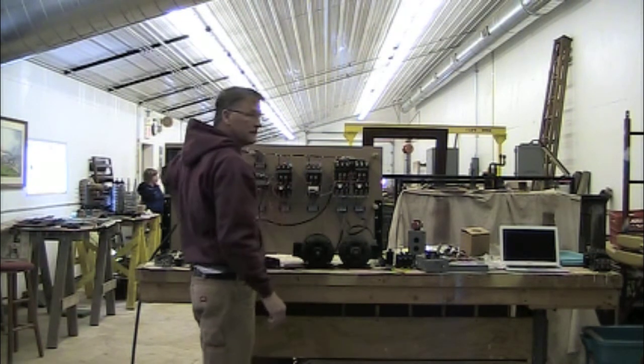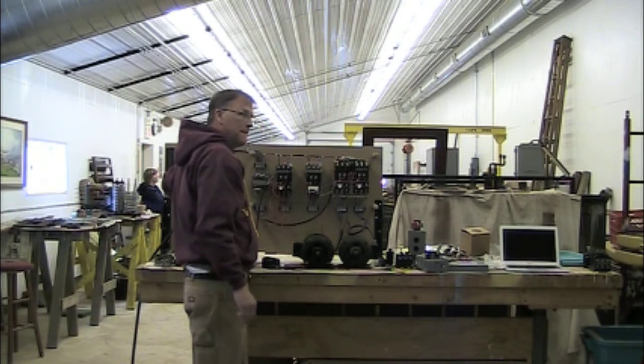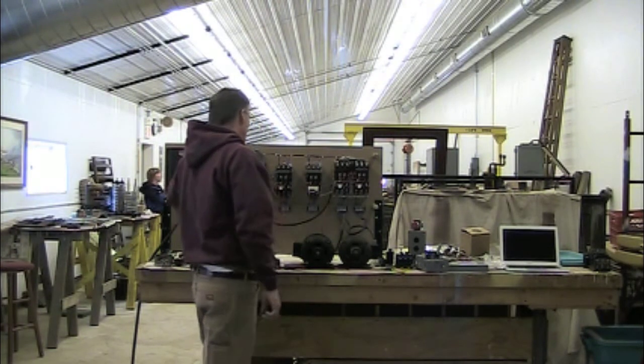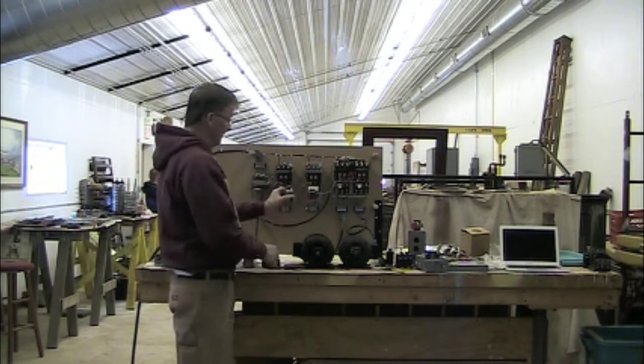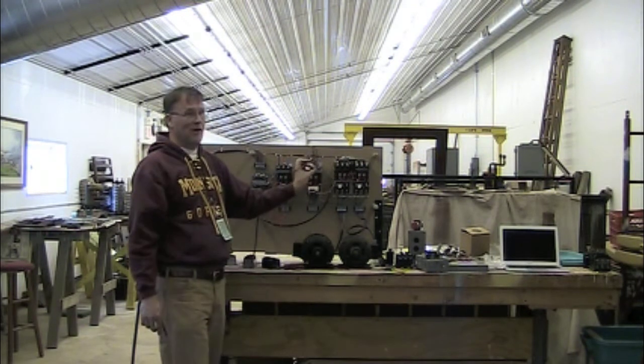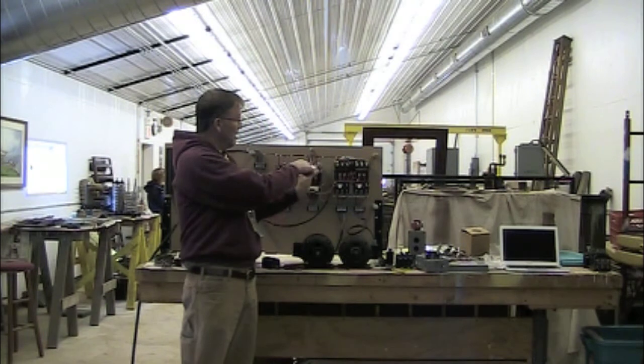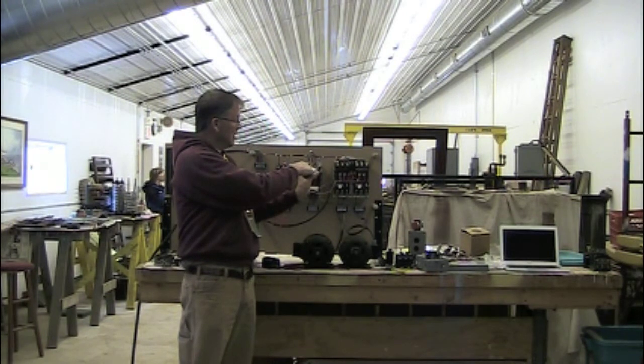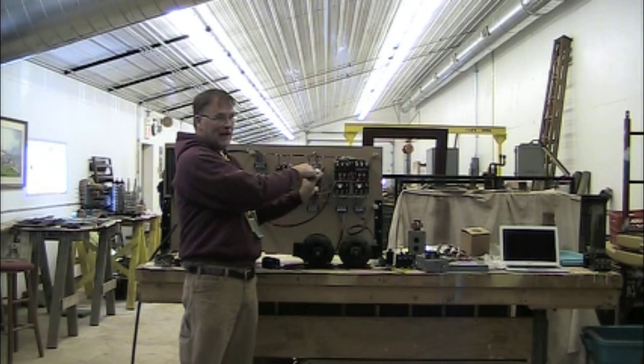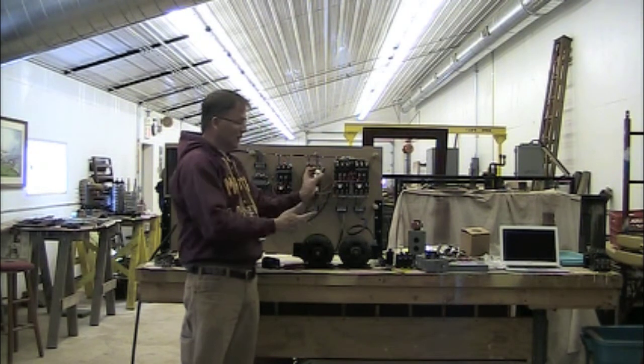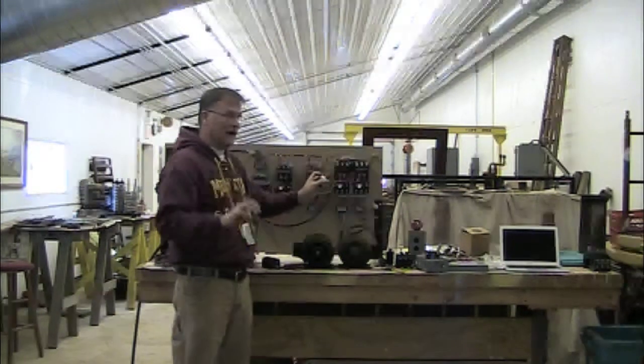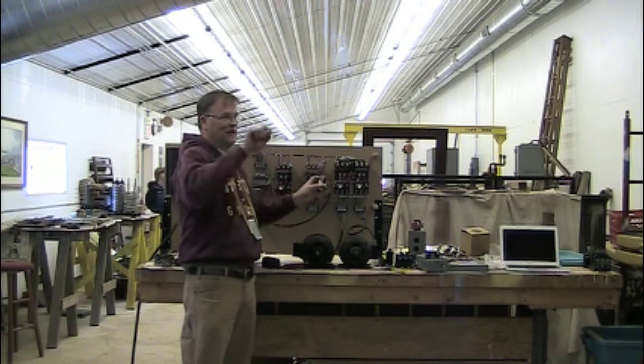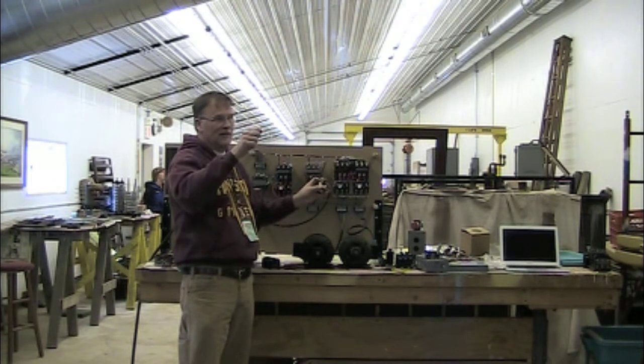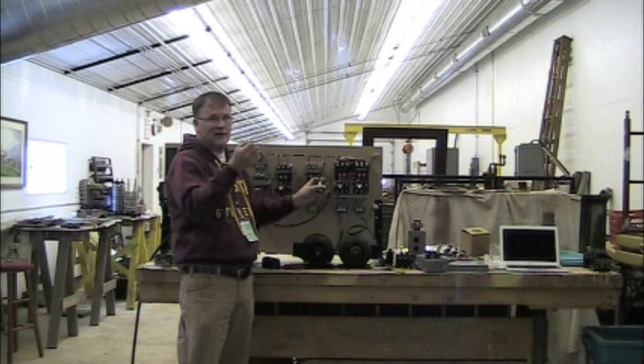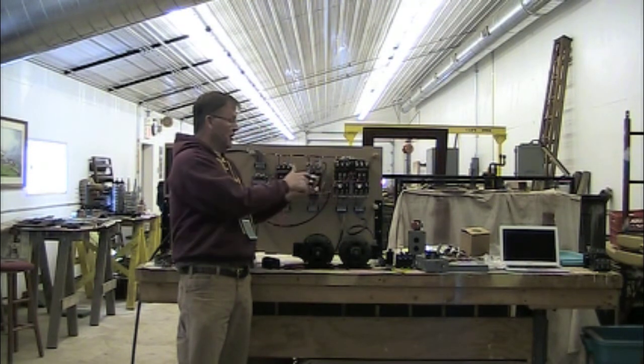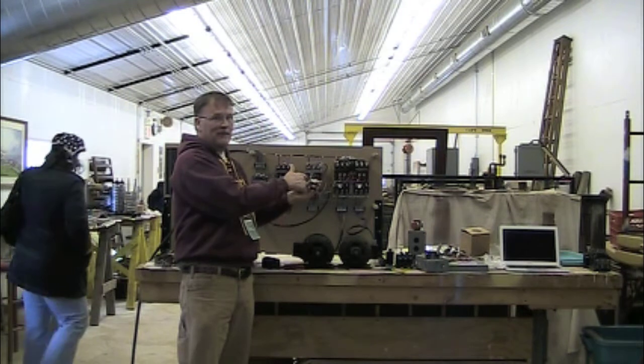That switch. That one's a breaker for me. Yeah. And so this little one, it's the exact same thing. It's all the same little components. So this is just one set of normally open, normally closed contacts on here, and it's like the maintained state one, but this is actually 3-state. It's 1 position, mid position where nothing happens, and then the 3rd position. But it's just a different operator body, same set of contacts.